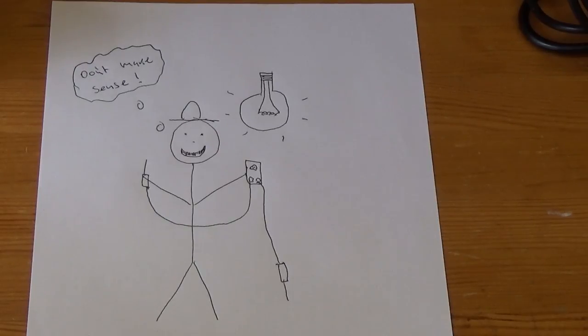As a general rule, conductors, the resistance of a conductor will increase with the increase of temperature. This is what we call the temperature coefficient. The temperature coefficient is the rise in temperature of one degree of a one ohm resistance, and then we take that figure and we can use it to calculate what the resistance is going to be at a certain temperature.